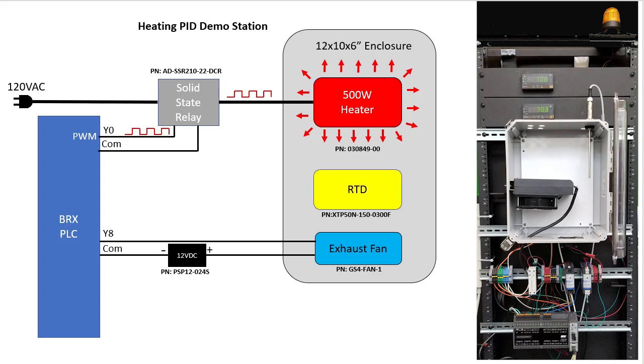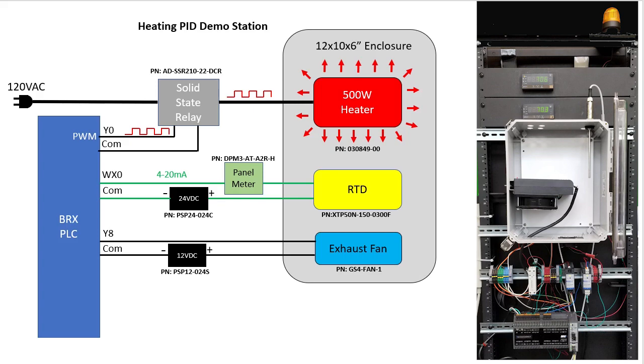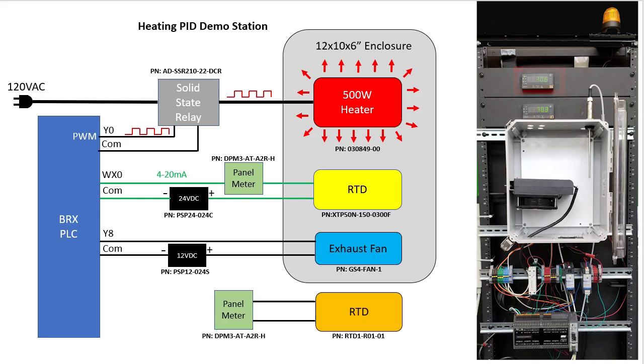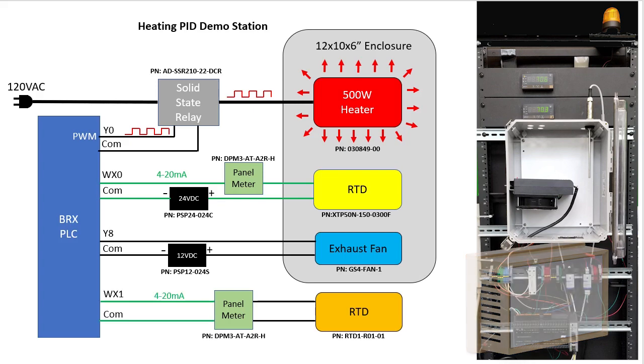This RTD sensor provides a 4 to 20 milliamp signal so we can run it directly into an analog input on the BRX PLC. I added a digital panel meter here so I can see at a glance the temperature inside the enclosure. It isn't required, it's just for my convenience.